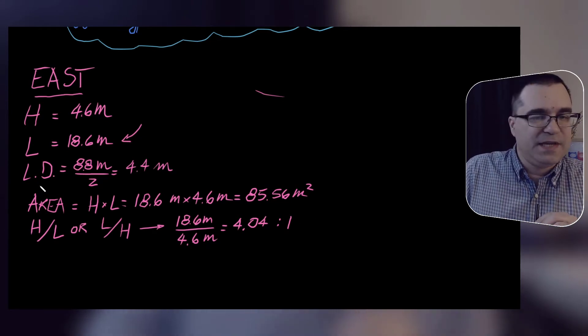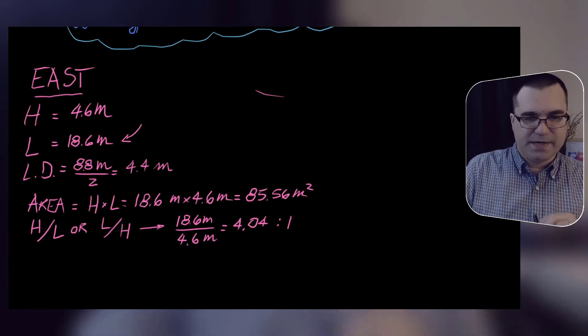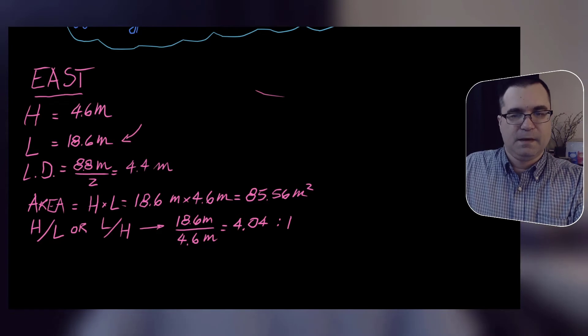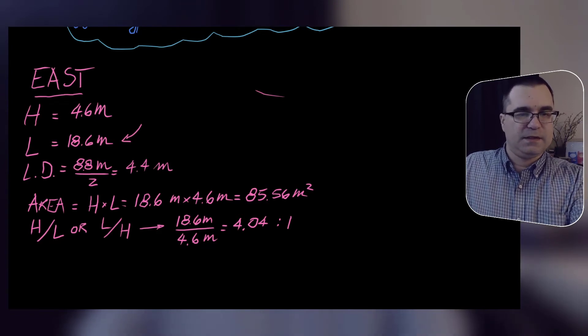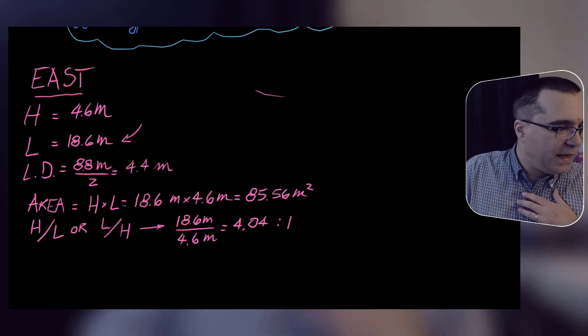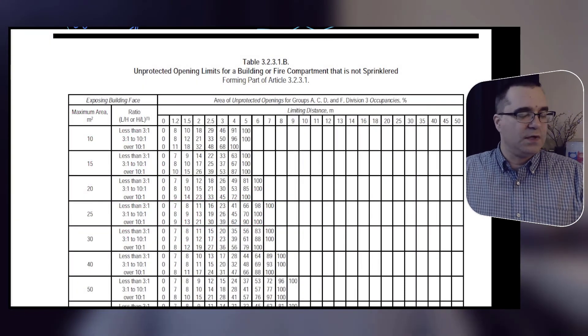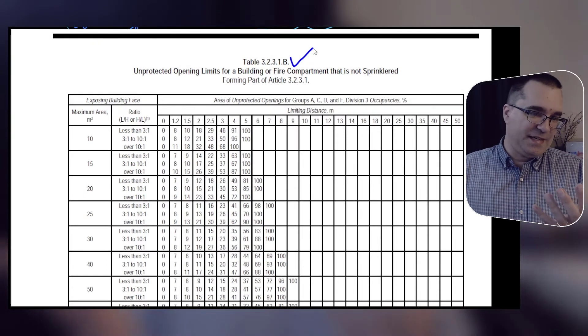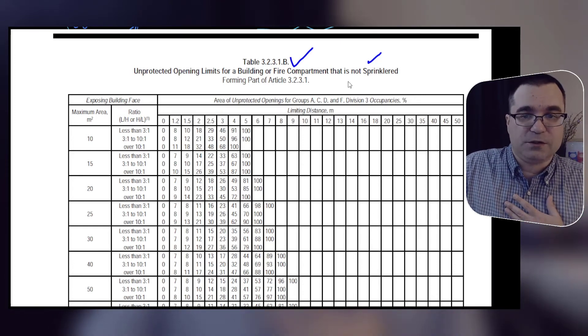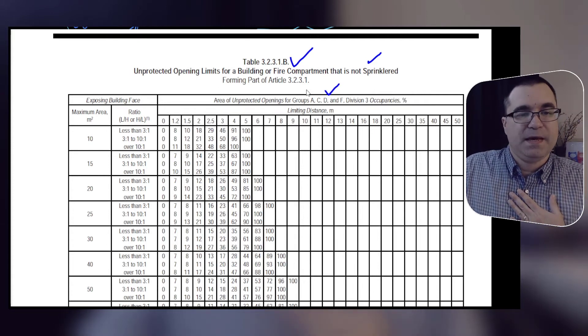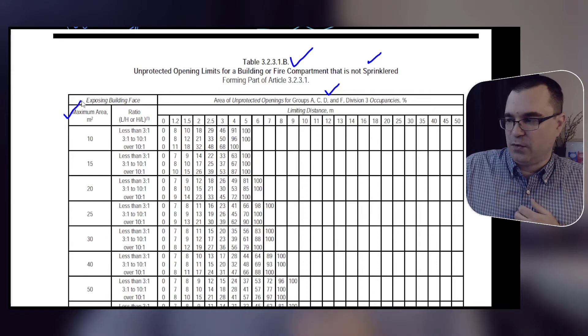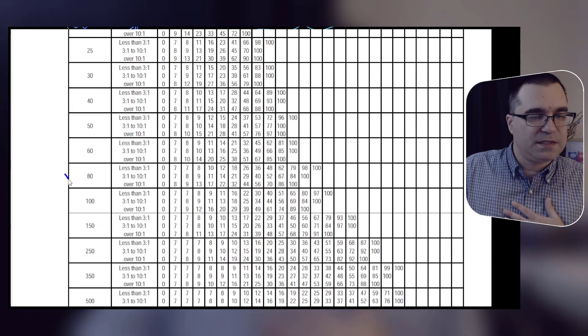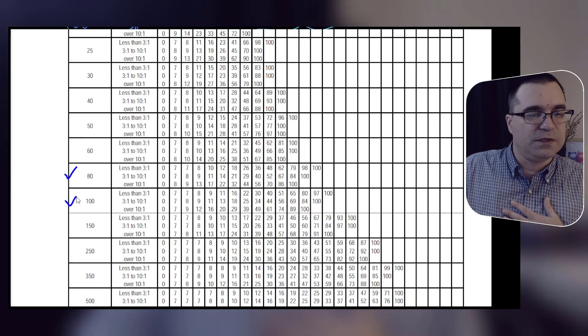So if we now bring up the table, I claim that the table we should be using is 3.2.3.1b. That's because our building is building A, not sprinklered, and it's also an A occupancy. Now for area, we have to figure out which area to use. We calculated an area of 85.56, so we have either 80 or 100 as options.